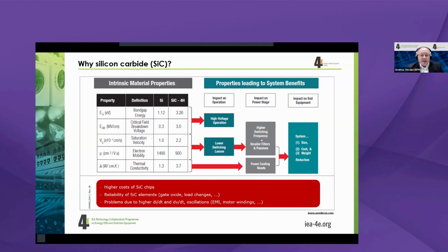Not that the silicon carbide elements are less reliable, I would say. There is a missing experience on how reliable they are. There is a missing experience on how to predict the lifetime of silicon carbide elements. And due to the higher power density and the higher operating temperature, there are also different types of failure cases. And due to the higher switching speeds, problems can arise in the end equipment; especially the higher change in voltage when switching on and off can have an impact on motor windings and an impact on EMI.